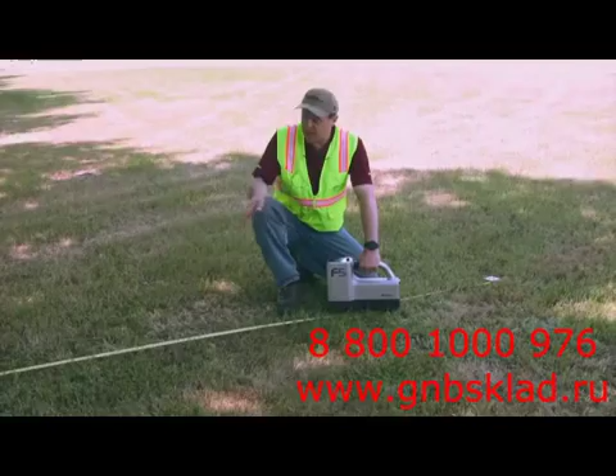So one thing we want to verify now, we want to make sure that we told this handheld receiver which transmitter to look for. So we go to the transmitter selection menu right here. I've got a myriad of choices I can grab. I need to grab the TensiTrak option. That's the lower middle of the bottom menu. Click it. I've just now told this handheld receiver to look for the TensiTrak device. Now we need to calibrate it.